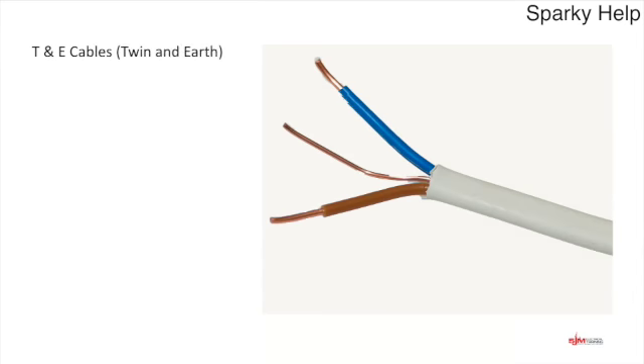But what about twin and earths, I hear you say? Twin and earths have a different size CPC built into the cables. I guess then everybody out there is actually doing the adiabatic equation, because this doesn't follow table 54.7. So if we have a 1.5 mil squared twin and earth cable, the CPC typically is around 1 mil. So therefore everybody must be doing the adiabatic equation.